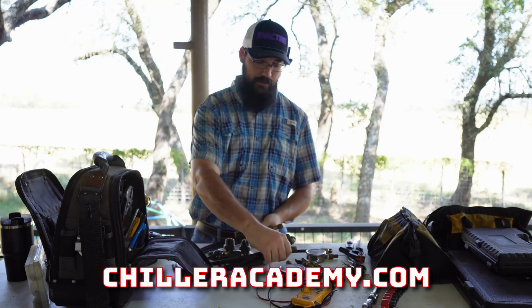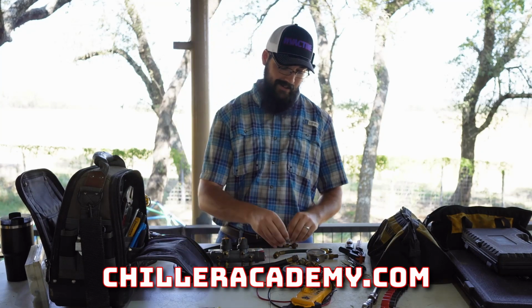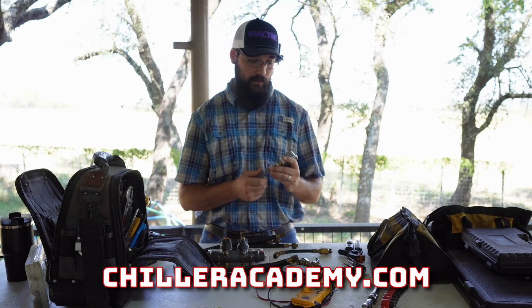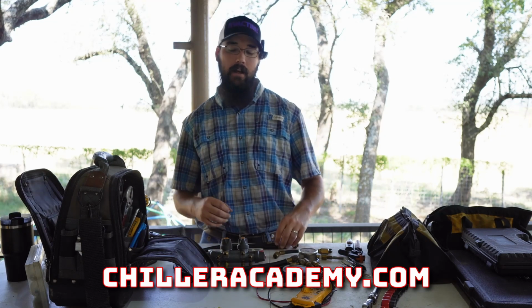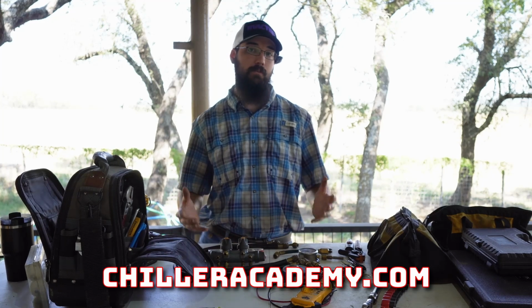Most of what we're doing on the chiller side, we're moving really large volumes. And a lot of the equipment we service doesn't have Schraders in it. So there's no need to have a Schrader, and we need to be able to move as much volume as possible, as fast as possible, to be efficient. That means that all restrictions need to be removed as much as possible.